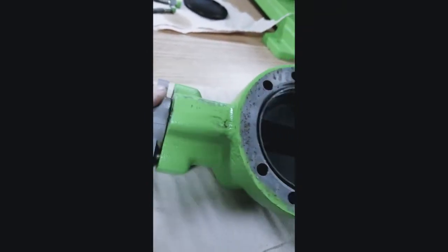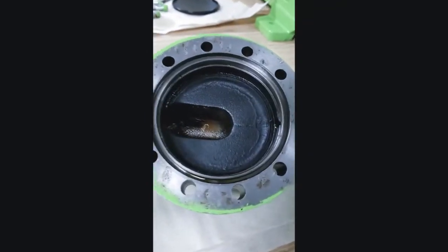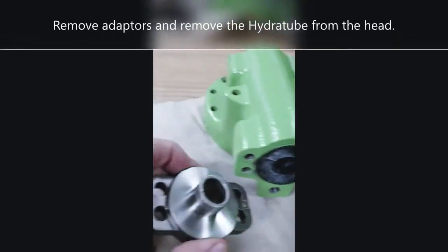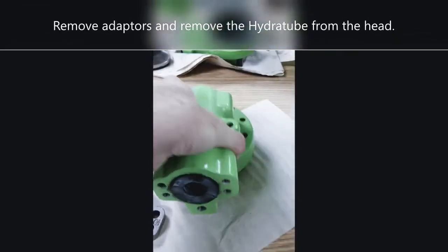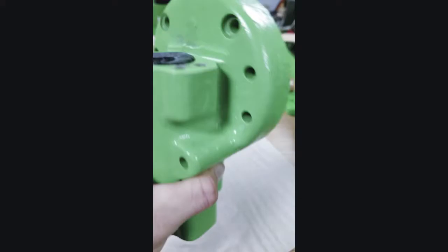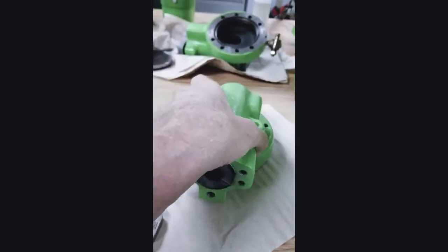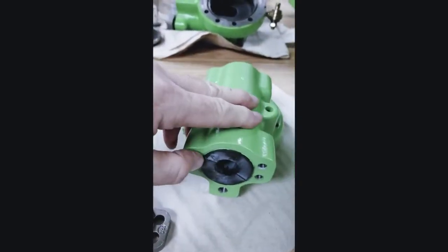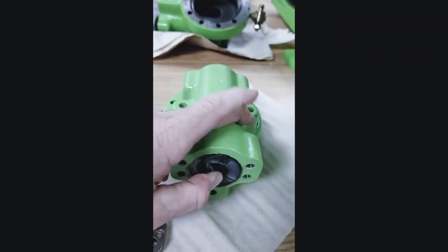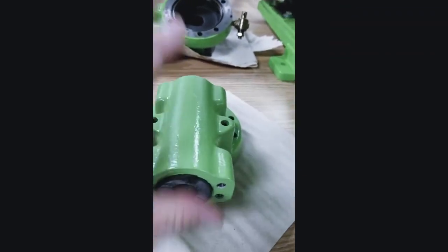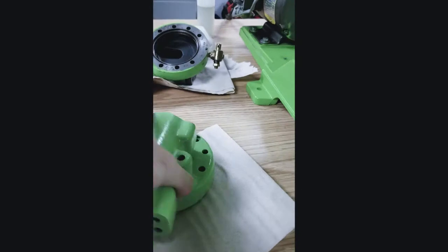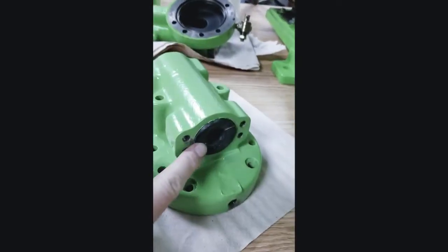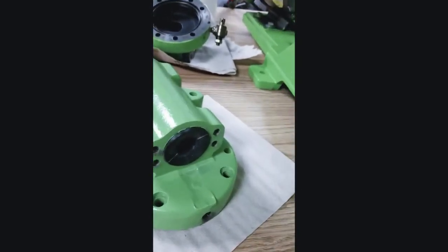My next task will be to remove the adapters so I can then take out the tube. Okay, I've removed my adapters from both ends of the pump head, the Hydratube head. You can see I'm ready to get to that tube. So now I'm just going to start at one end, and I'm going to fold this in all the way around, and I'm going to push it into the head and force it in, and then I should be able to get a hold of it from the other end and pull that tube out.